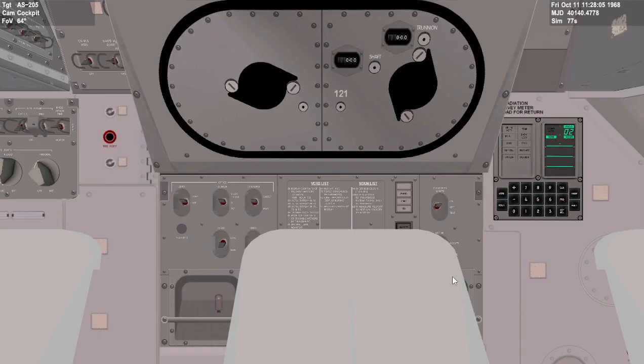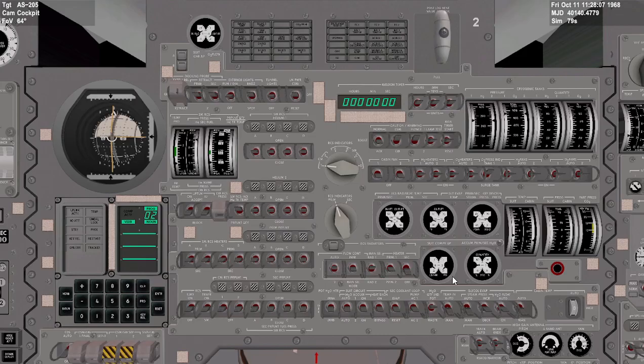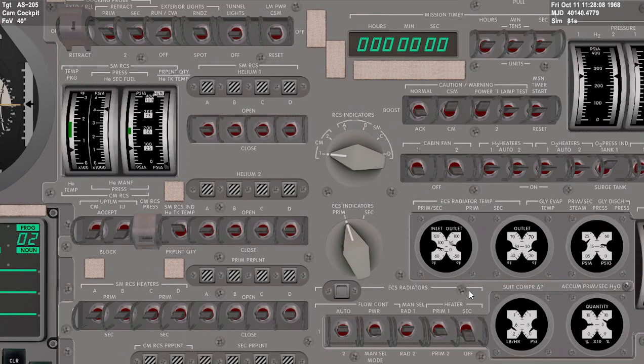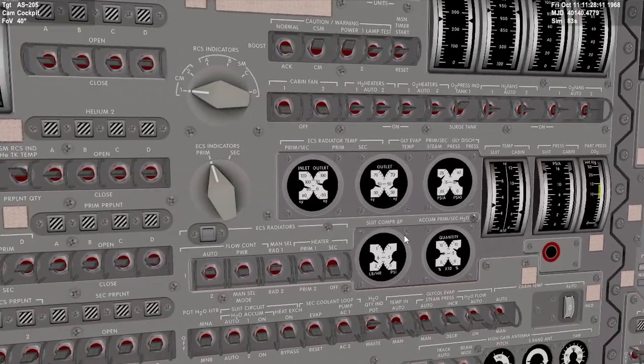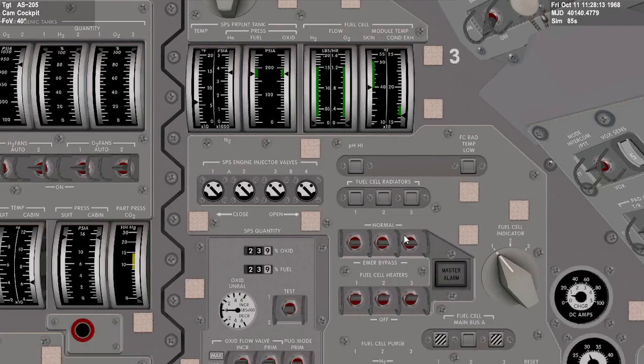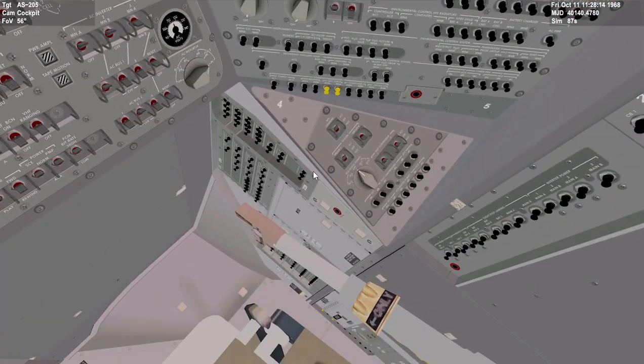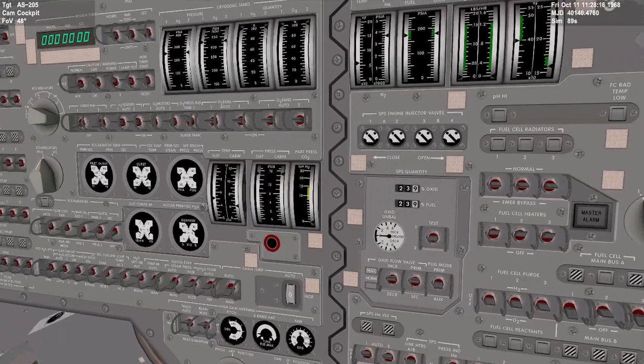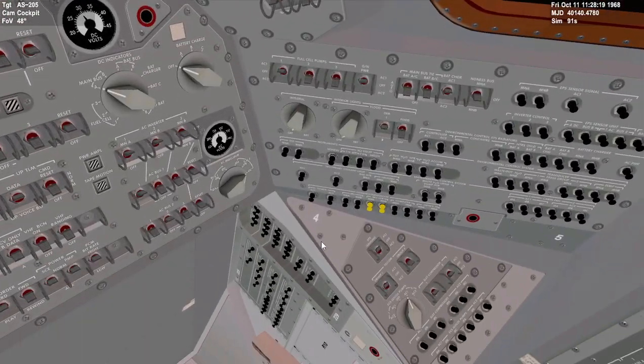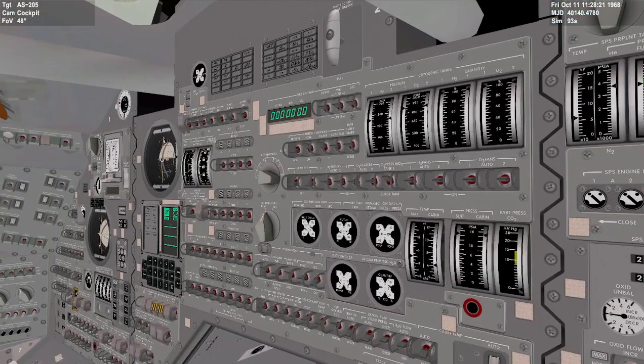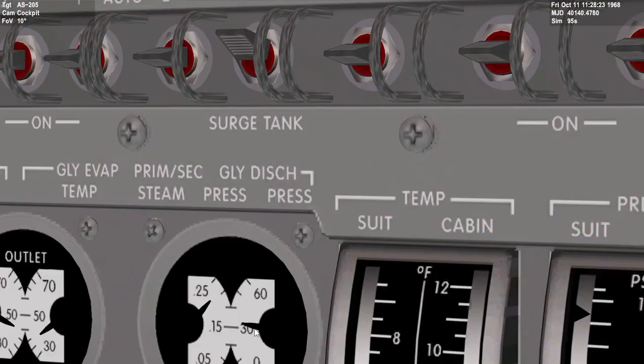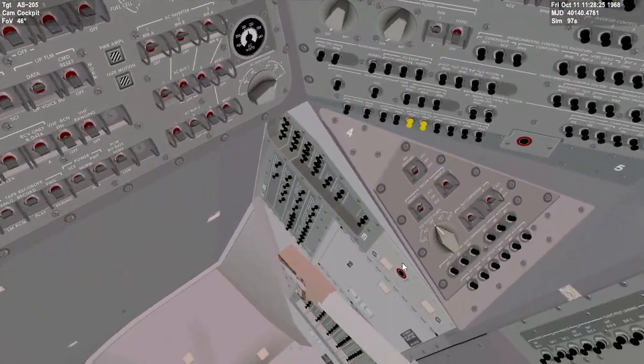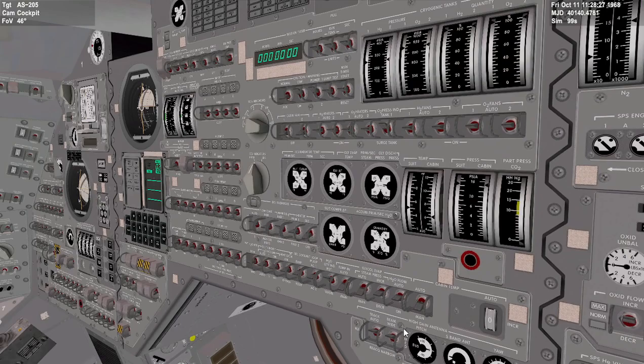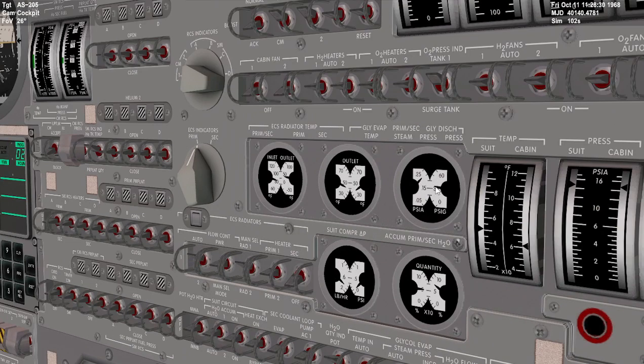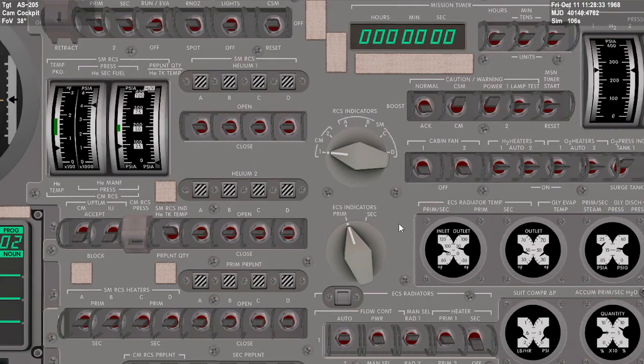We're now going to go through the primary loop activation. This loop is a little more sophisticated, but it's essentially the same thing. We're on primary. We're going to verify that the glycol loop holds with pump 2. Set it to off. We could see it slowly spin down, and then go to pump 1. It was not under its own power earlier, but now that we've activated the pump, it is now under its own power, and so if we take the pumps off, it will not hold the pressure anymore.